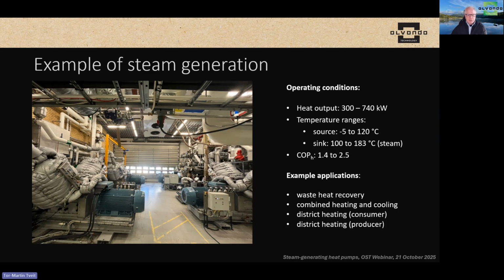Example applications: waste heat recovery, combined heating and cooling, district heating as the consumer so we can generate district heating, or as a consumer so we can use district heating as a heat source to generate steam. We have one application using district heating to generate ten bar steam. We can also generate district heating from a cold source. In this application, we get waste heat from cooling compressors at around 40 degrees, and we lift that heat up to about 10 bar. Now they've reduced the steam pressure slightly, so it's about 9 bar steam that we're generating here.